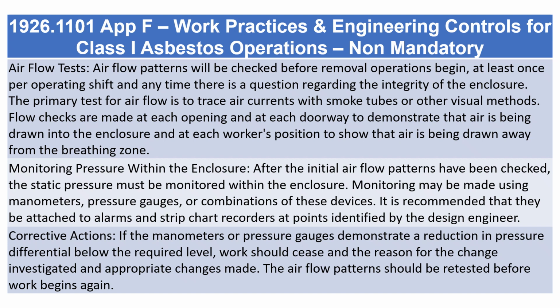The primary test for airflow is to trace air currents with smoke tubes or other visual methods. Flow checks are made at each opening and at each doorway to demonstrate that air is being drawn into the enclosure and at each worker's position to show that air is being drawn away from the breathing zone.